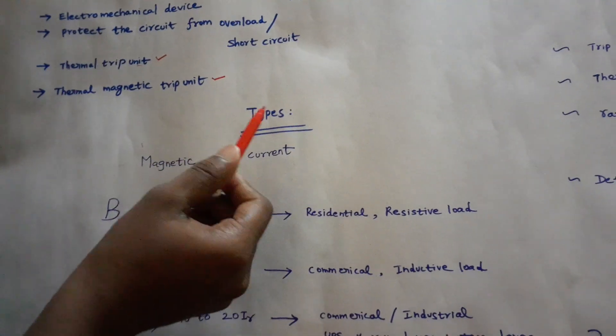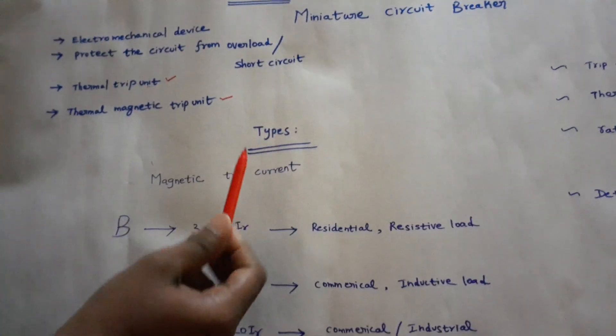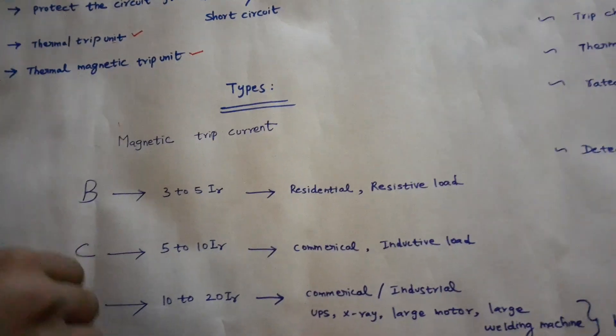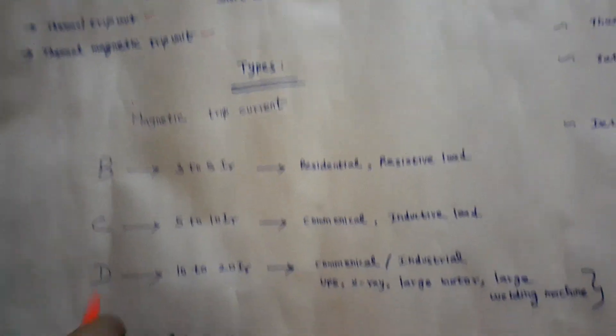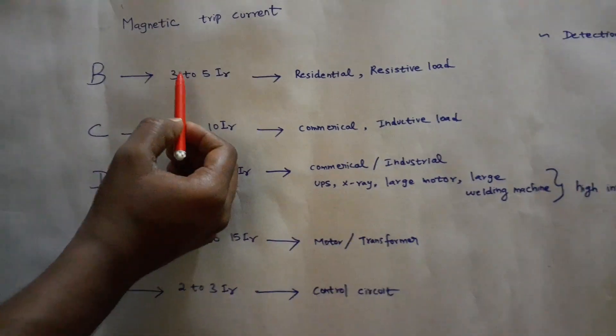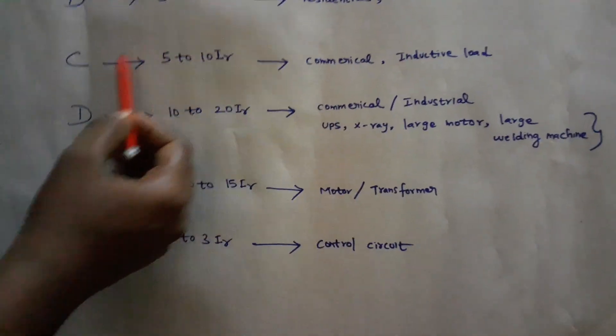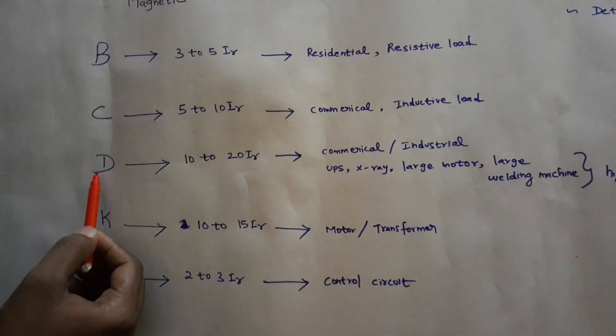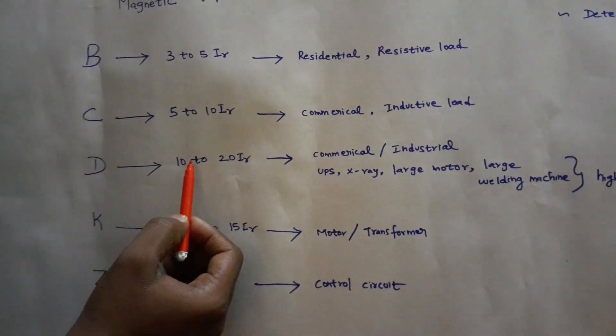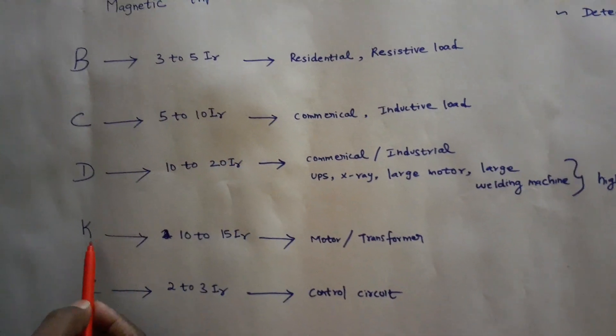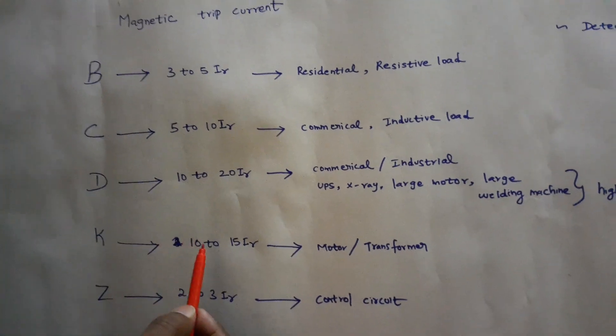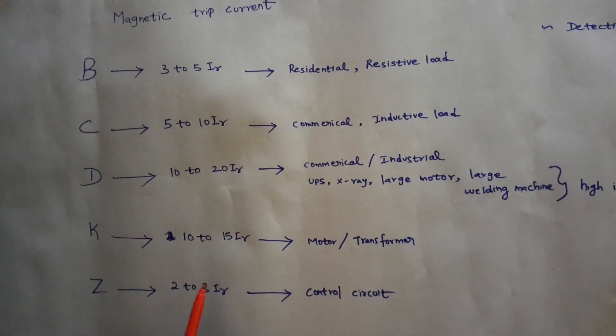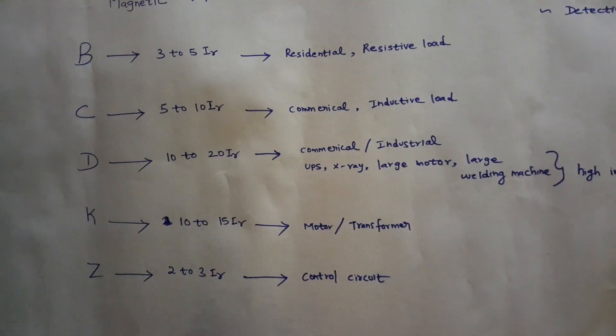The types of MCB are B, C, D, K, and Z. B type trips at 3 to 5 times the rated current. C type trips at 5 to 10 times. D type trips at 10 to 20 times. K type trips at 10 to 15 times. Z type trips at 2 to 3 times the rated current.